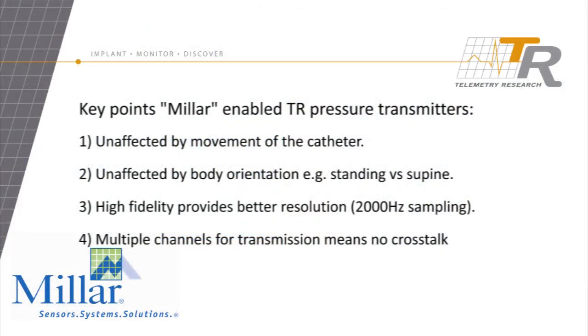In this video, we've introduced a number of key features associated with the new Millar-enabled TR pressure transmitters. The first point is that movement of the animal, which causes movement of the catheter, does not affect the signal quality. The second point, that orientation of the animal, such as moving from standing to supine or during even exercise, doesn't cause movement artifacts. The third point is that the high fidelity of the solid-state sensor, with a very high frequency response and sampling at 2000 Hz, provides a very good fidelity of the waveform.